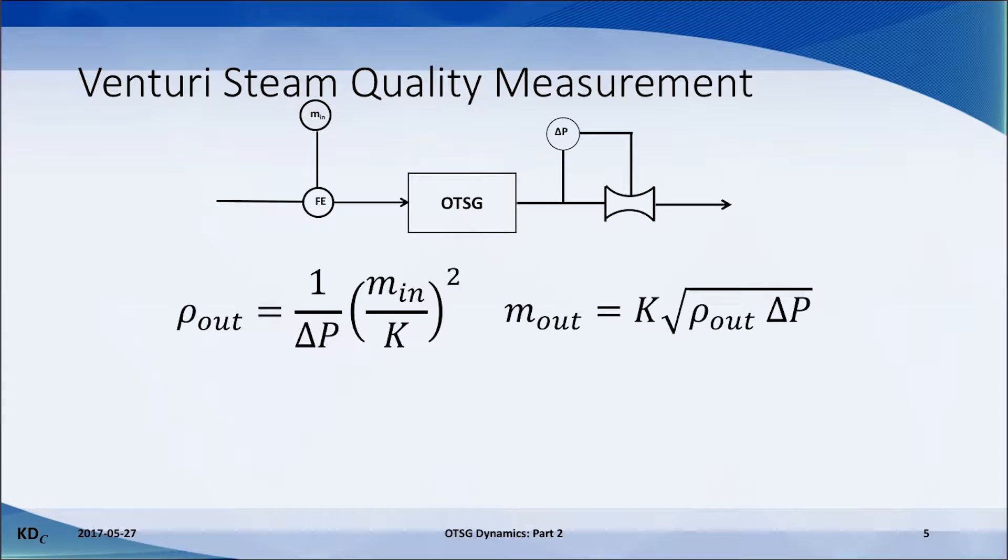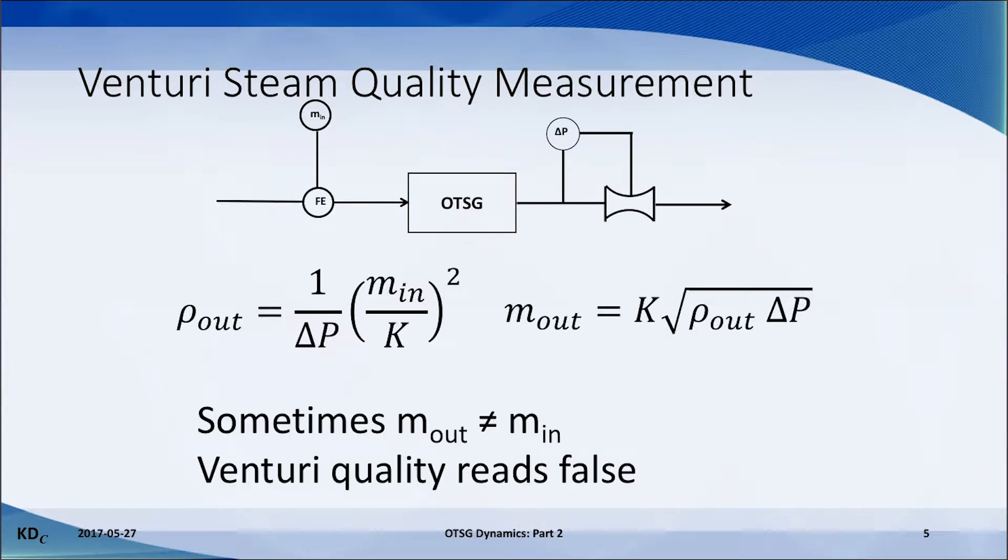However, if the mass flow rate out of the pass is not equal to the mass flow rate into the pass, this inferred measurement will read false and give us the wrong density, and hence the wrong steam quality. There are several different correlations that are typically used to infer steam quality, but they all have the same general form as the simple one shown here.